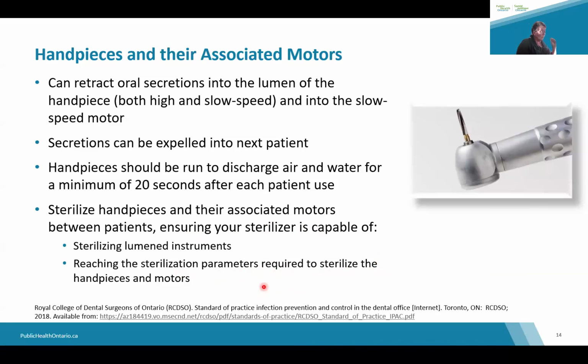And here is also important: you need to ensure your sterilizer is capable of sterilizing items that have lumens, because handpieces have lumens, and that it's capable of reaching the sterilization parameters described in the MIFUs. Some of the older sterilizers are not able to do this. So this is a really important aspect when it comes to the sterilization of handpieces.